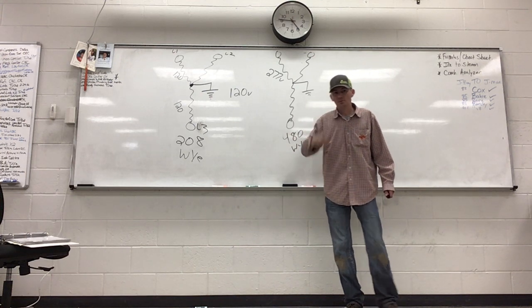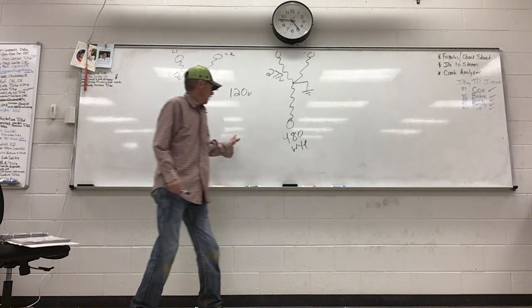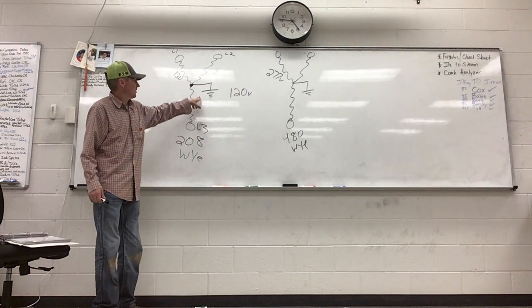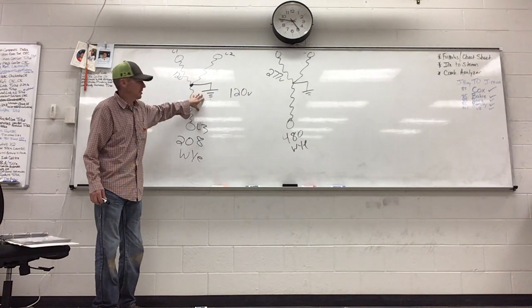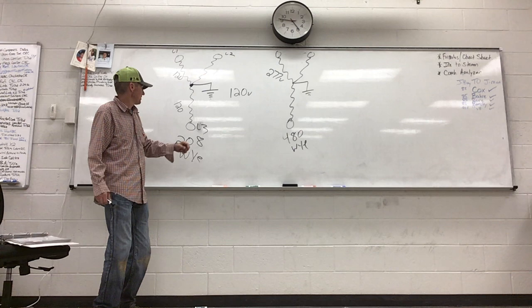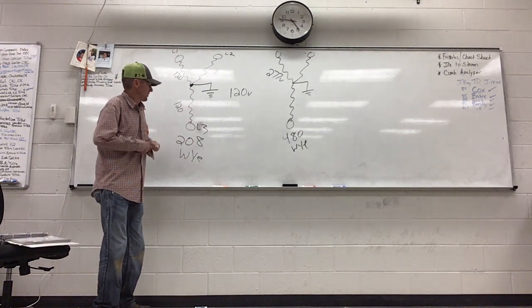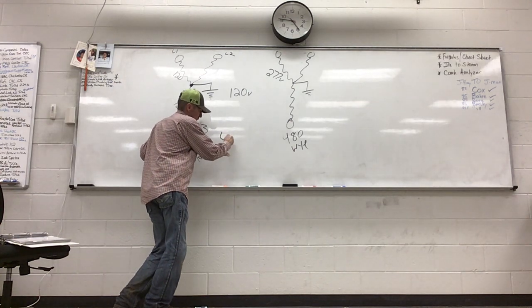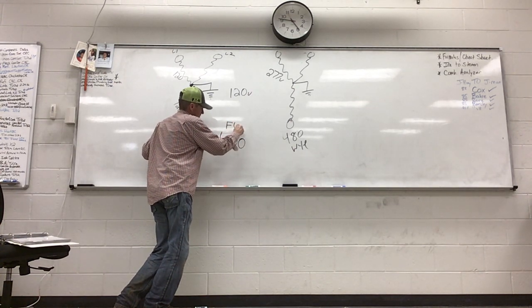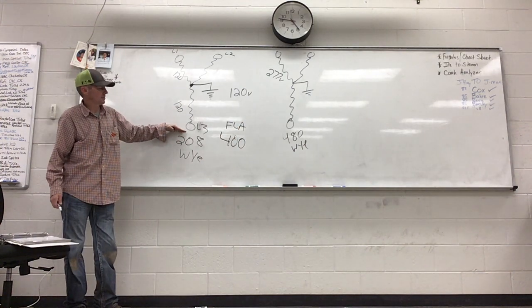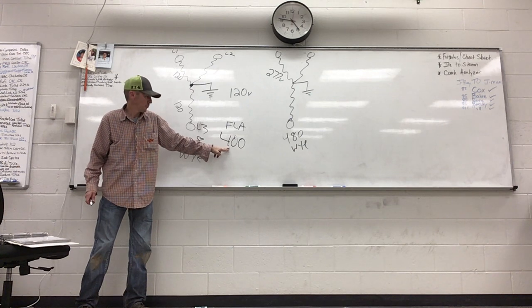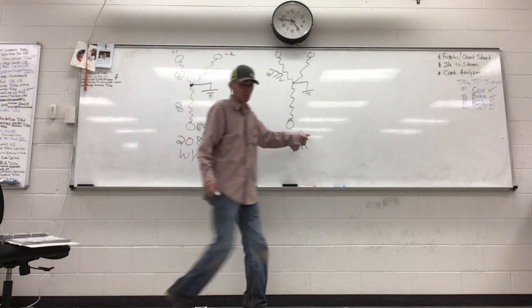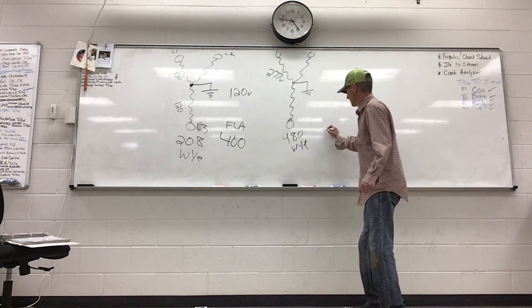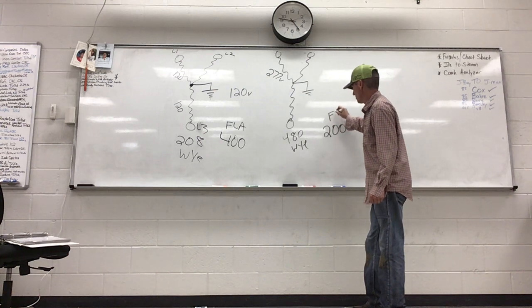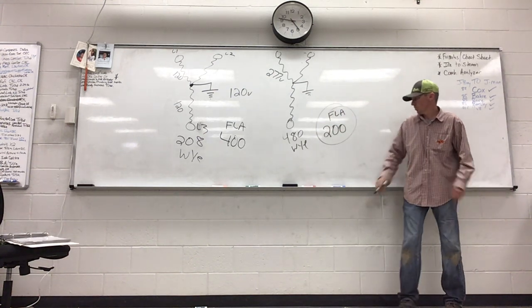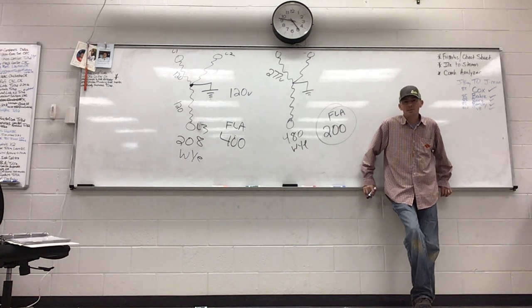And what I mean by that is when we start figuring in Ohm's law and stuff, if I have like an RTAA, or a chiller, some kind of screw machine, a 100-ton screw machine, and it runs on 208, well, its full load amps is probably going to be like 400 FLA or whatever. I'm just making something up. So if at 208 it has an FLA of 400, what's it going to be when we double it? If you said it's going to cut it exactly in half, you would be correct. So the amperage cuts in half as the voltage doubles, right?